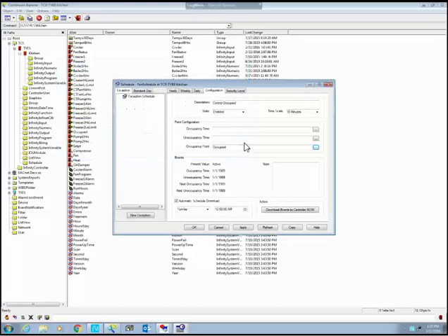And if we go back, this is the point that this schedule is going to turn on and off. It's going to turn on and off without any other programming, this occupied. Right now, let's do a standard day just to make it work. 8 to 5. Okay, it should work today.